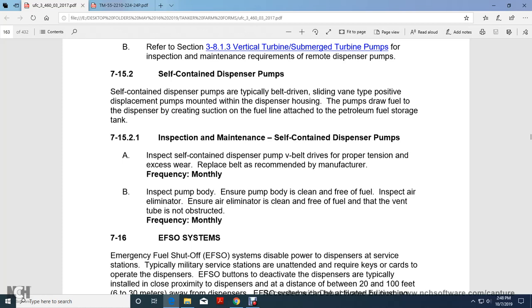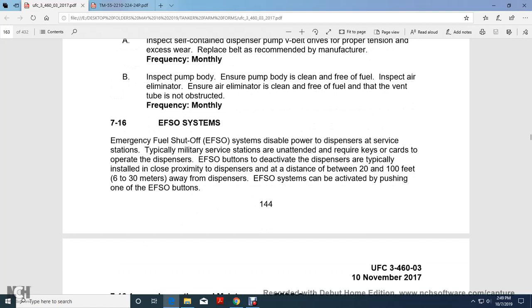7-15.2.1 inspection maintenance of self-contained dispenser pumps. Inspect self-contained dispenser pump V-belt drives for proper tension and excessive wear, and replace the belt with one recommended by the manufacturer, monthly. Inspect the pump body to ensure it is clean and free of fuel, and inspect the air eliminator. Ensure the air eliminator is clean and free of fuel, and that the vent tube is not obstructed, monthly.